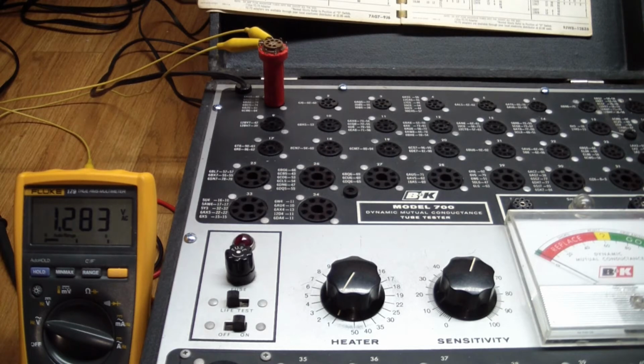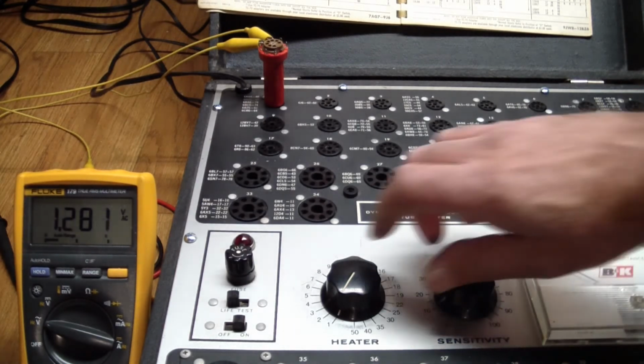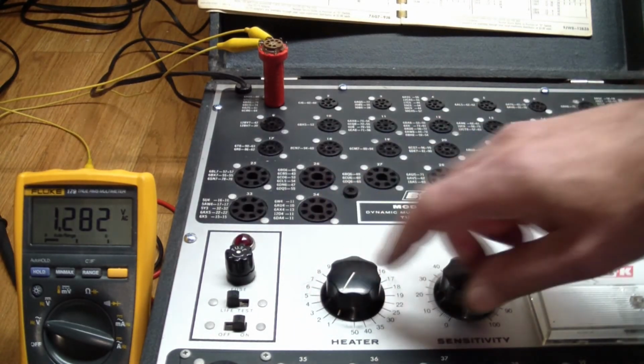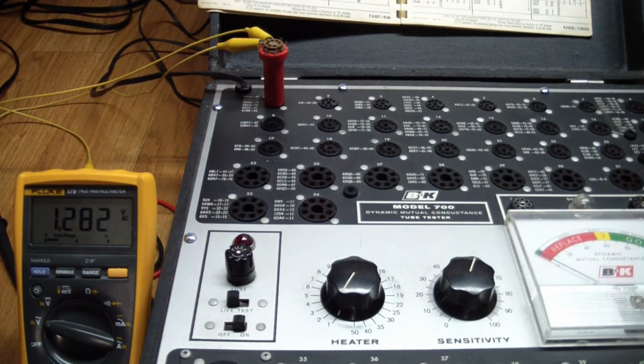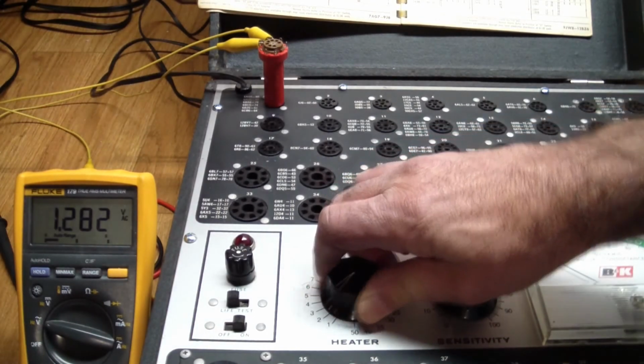1.28, but since we are measuring this without a load, it is expected for the voltage to be high. I mean, this isn't even that high. It's only about, just under 10% higher than specified, so this voltage is good. So I'm not going to go through every voltage. Even though when you're doing the testing you probably should go through every one, but for the sake of brevity I will just jump around.